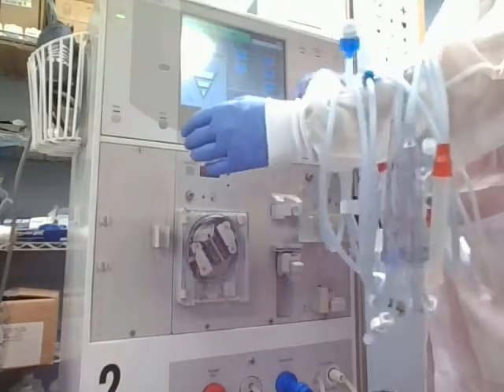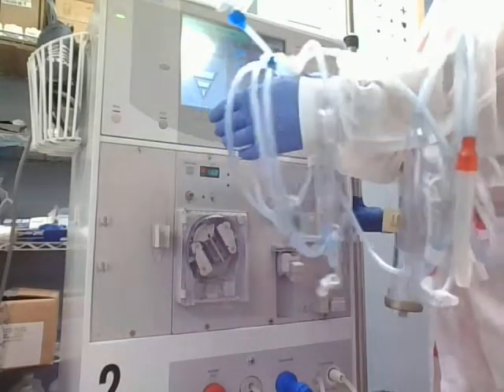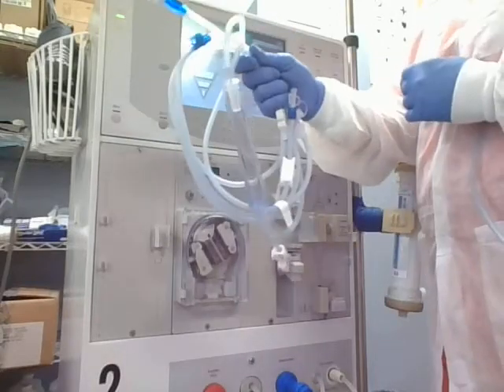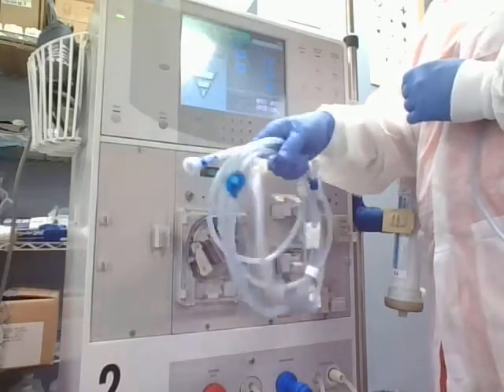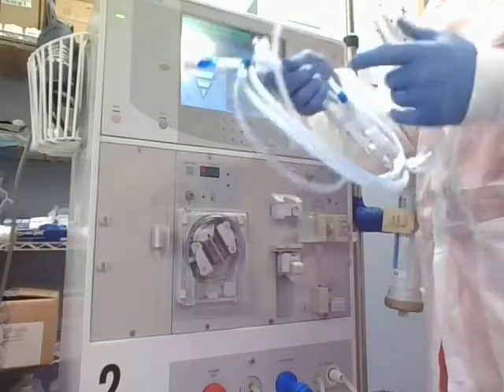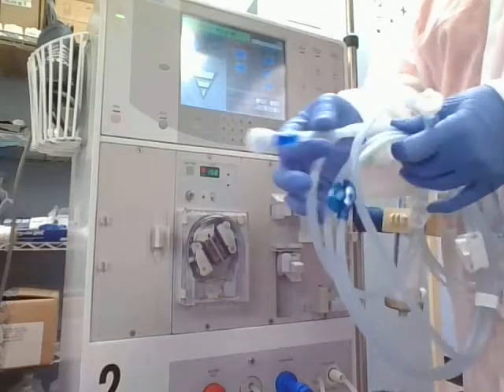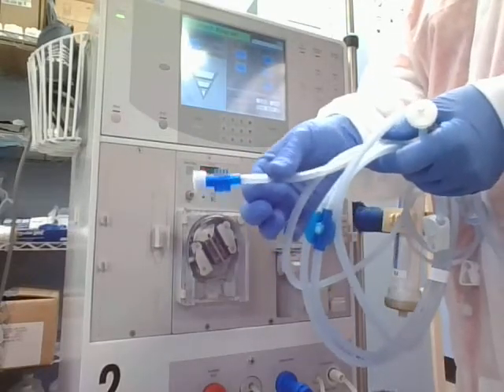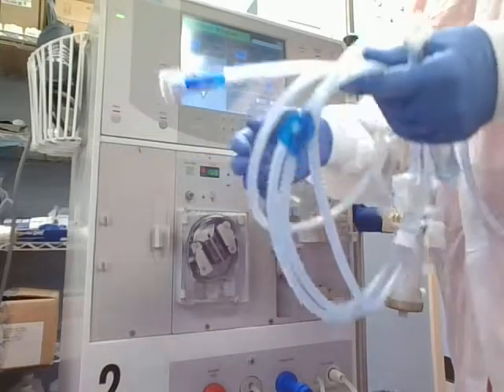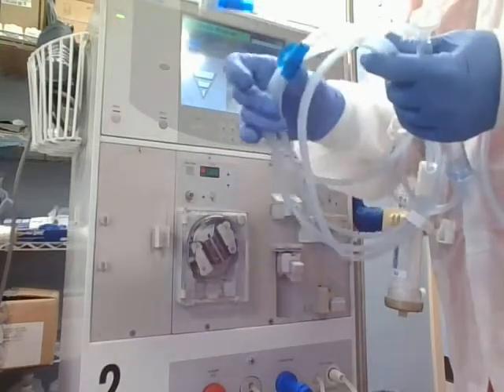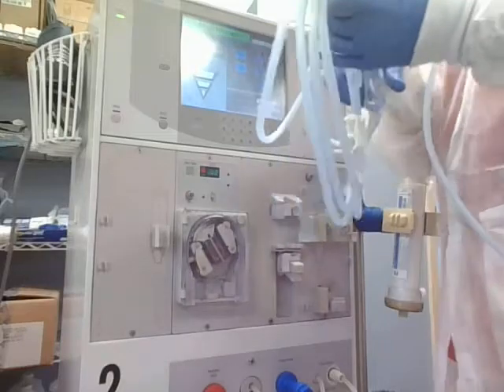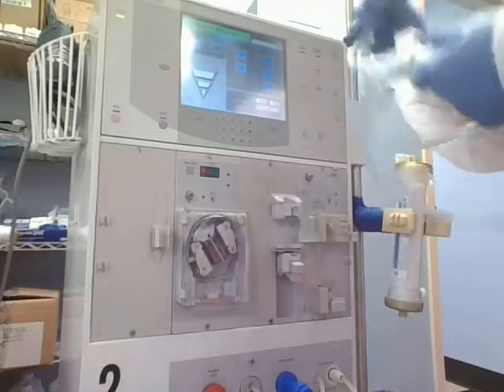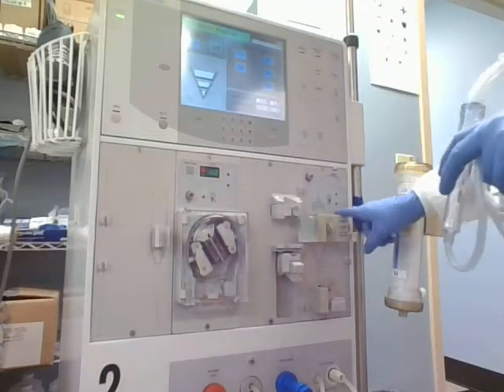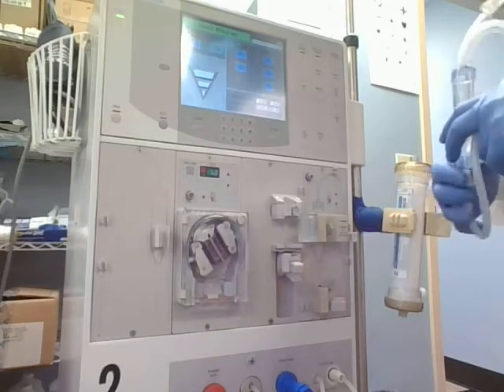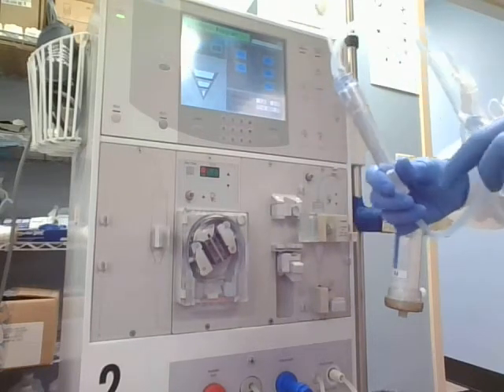So I place my lines on my arm, and I always get my venous line first, and I know this is venous because it's blue. You notice that these are color-coded. My dialyzer connector and my patient connector, they are both in blue. So to start off with, the first thing I'm going to do is make sure that my air foam detector is open. That's where my venous drip chamber goes.